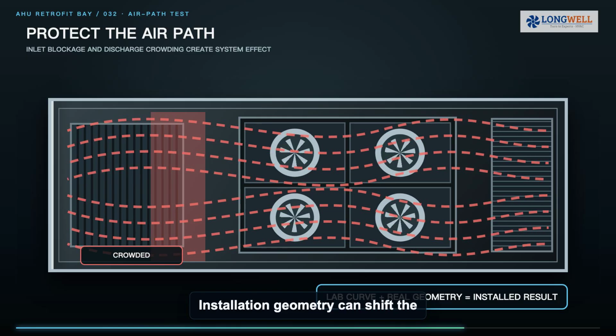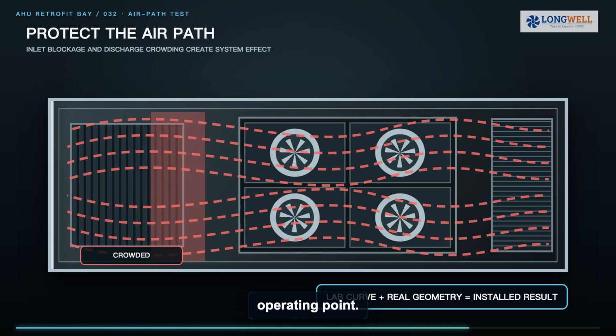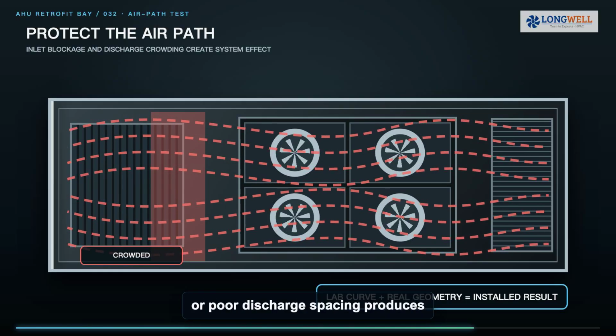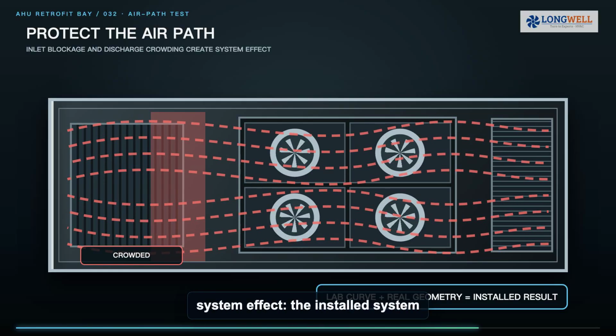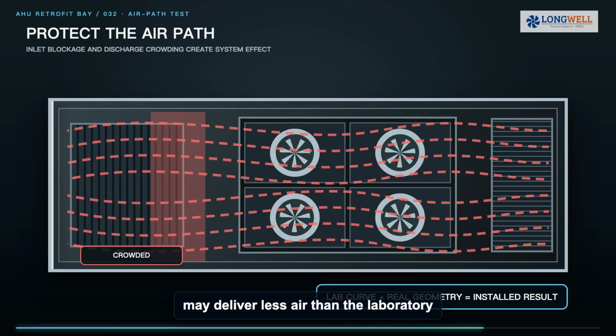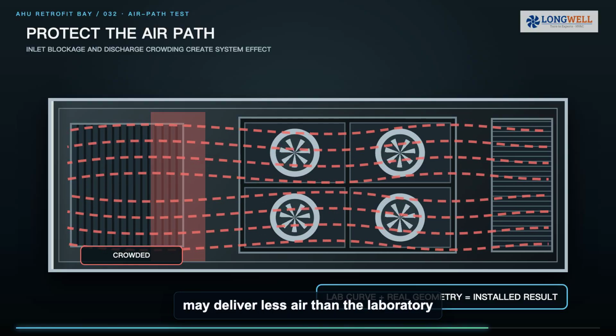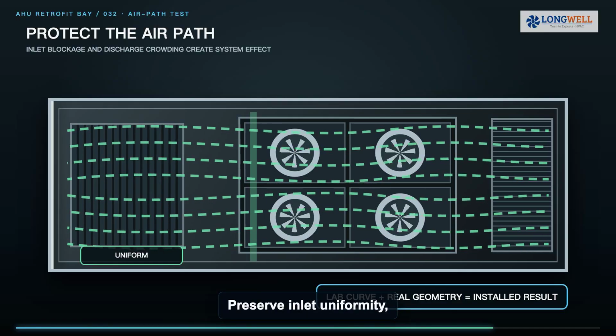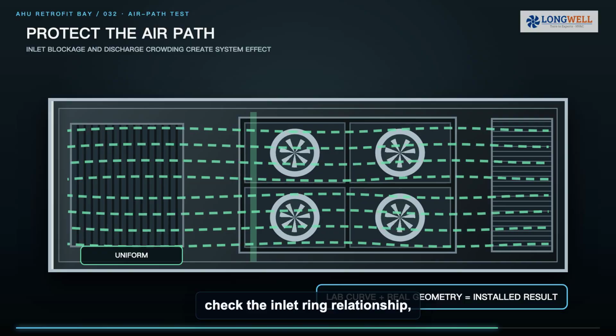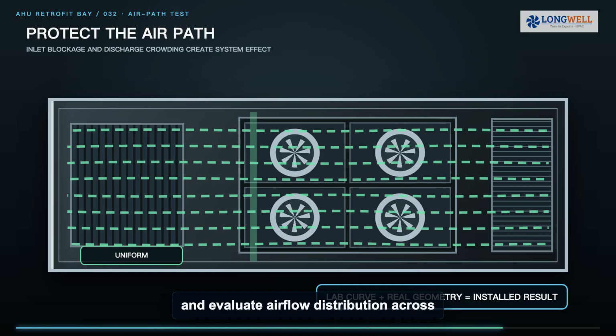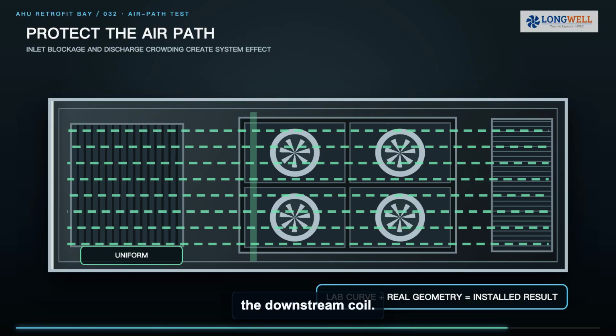Installation geometry can shift the operating point. A blocked inlet, abrupt transition, or poor discharge spacing produces system effect. The installed system may deliver less air than the laboratory curve suggests. Preserve inlet uniformity, check the inlet ring relationship, and evaluate airflow distribution across the downstream coil.